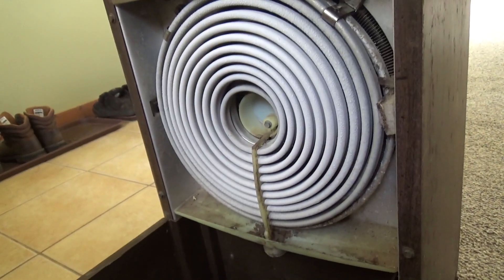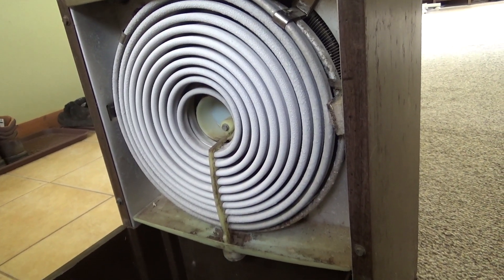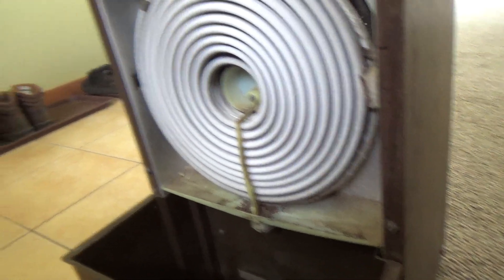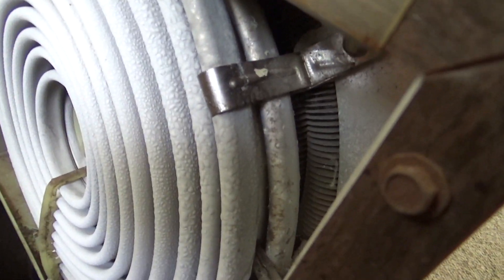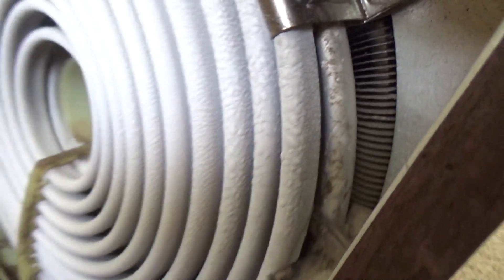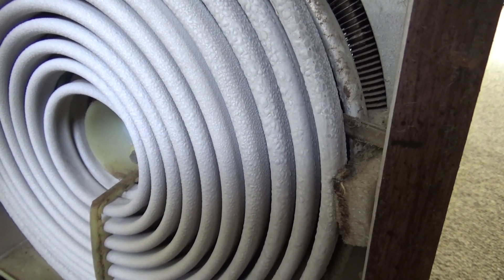And you can see now we're iced up completely. I'll give it a few minutes and it'll unthaw and start pulling moisture. What's also interesting is that if you look at the coil, the cleanliness of it varies. The second layer is really going to run here, but the third layer is clean. So that would lead me to believe that the water has been running down this coil for a long time, and not the second layer. It might just be the way it is.